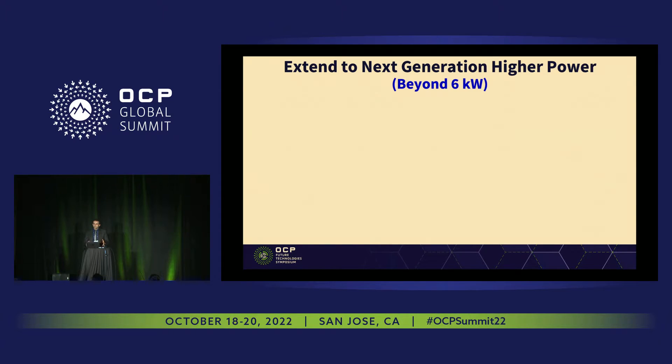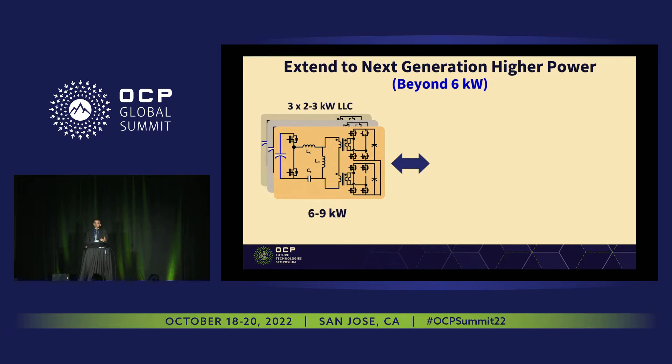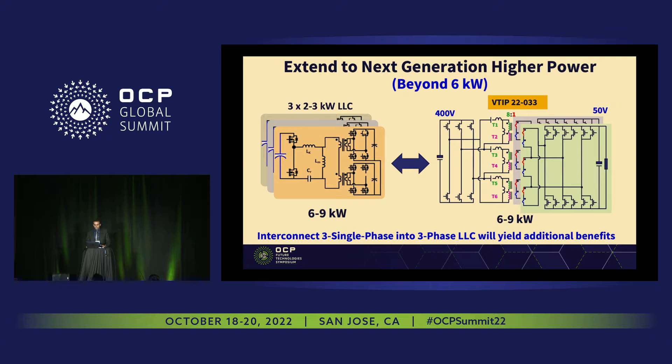We wanted to take this 3 kilowatt concept and extend it beyond 6 kilowatt. By extending to higher than 6 kilowatt, we're not looking to just parallel some DC-DC converters and take more space. We're looking at fitting 6 kilowatt in the same footprint as a 3 kilowatt — doubling the power density while keeping the same or even slightly higher efficiency.